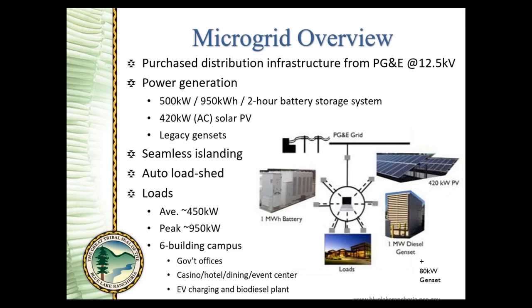If it's a 3-hour outage, we're really not going to do any load shed. If it's a 3-day outage, we're going to do some load shed. And if it's a 3-week outage, we're going to take it down as far as we possibly can, and only have those life, health, and safety level needs met with our power system, so we can extend it as long as possible.